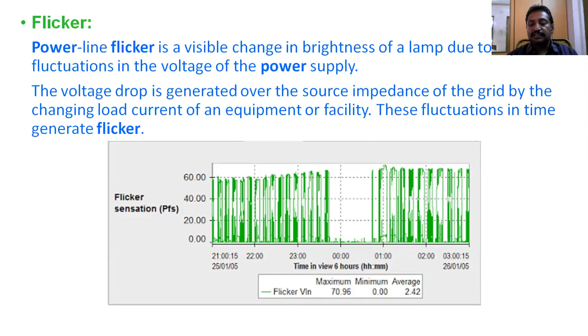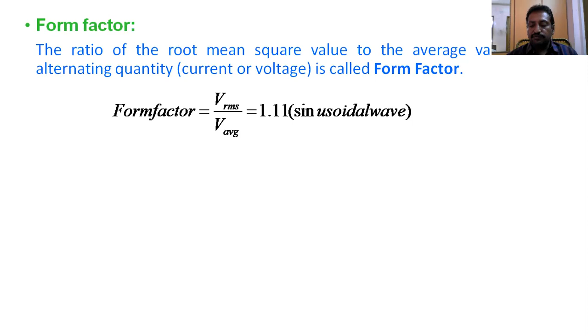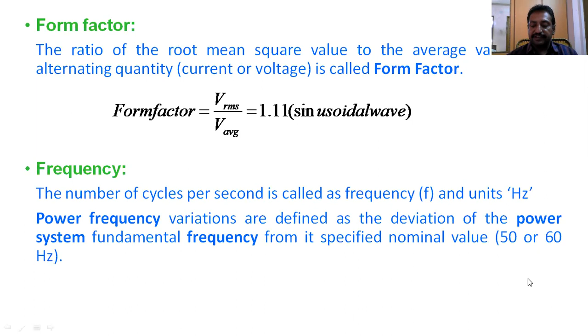Form factor. It is the ratio of the RMS value to the average value, called the form factor. It is a fixed, derived value for a sinusoidal wave, 1.11. Frequency. Everyone knows that frequency, the number of cycles per second, is called frequency. Whereas in the case of power frequency, it is the deviation of the power system fundamental frequency from its specified nominal value, 50 or 60 Hz: 50 for India, 60 for the USA. So this is called frequency in the case of power quality.